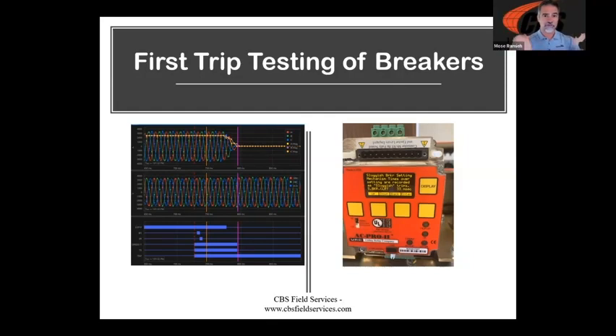Now, I want you to picture you're going to sit in that squat for 10 minutes. And then think about how much energy you're going to be able to explode upward with, right? It's an interesting experiment because if you're being honest, it's going to be a little bit harder to get out of the bottom after I've been sitting there for a while. And that's what we ask our breakers to do, right? We ask them to go closed and stay closed until we need them to open, right? That might be being closed for a year, 3 years, 5 years. Once again, I think I've interacted with breakers that haven't been open since the day they were put in service, right? So once again, how do we know our breaker is going to operate well?